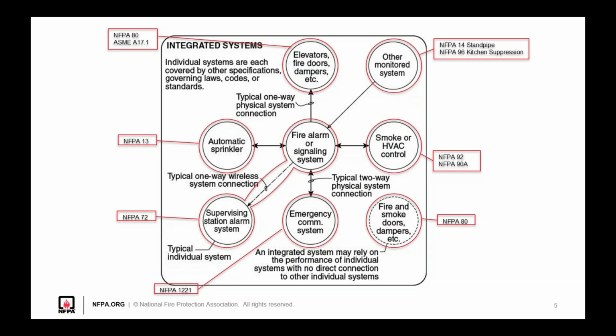So where you have systems like a fire alarm and a kitchen hood suppression system that are interconnected via a relay, you have the kitchen hood. When it activates, the relay will close, and then it sends a signal to the fire alarm system, which then responds accordingly. So in that case, the scope of NFPA 72 is going to cover the design, installation, inspection, and maintenance of the fire alarm system, while the scope of NFPA 96 is going to cover the design, installation, inspection, and maintenance of the kitchen hood suppression system. But neither of these standards are providing requirements on how these two systems must be integrated.